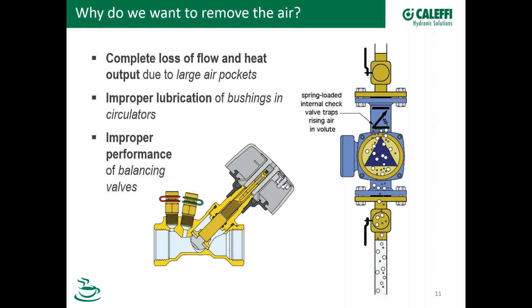Also, air in the system can cause problems with other products like balancing valves. For example, here's a cutaway. If you can imagine that you had air inside of this balancing valve, your pressure taps might not be picking up the fluid directly, and that could cause a problem also.